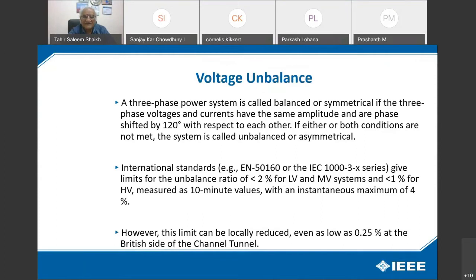International standards, for example the European standard EN 50160 or the IEC 61000 series, give limits for the unbalance ratio of less than 2% for LV and medium voltage systems and less than 1% for HV, measured as a 10 minute value with an instantaneous maximum of 4%. However, this limit can be locally reduced, even as low as 0.25%, at the British side of the channel tunnel.